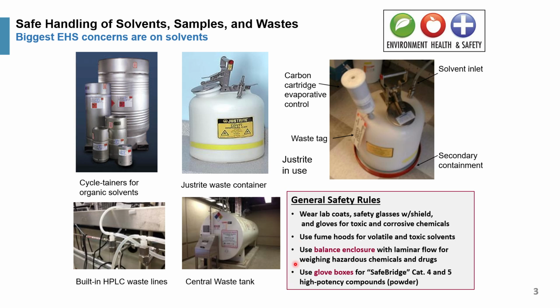Well, for weighing, you should use a balance enclosure because most pharmaceuticals are considered safe bridge category 3, meaning they're toxic to humans, and you cannot weigh them out in the open. If you weigh buffer, you can weigh it out on an open weighing balance. So these have laminar flow. You should not do it in a hood because the flow is too strong.